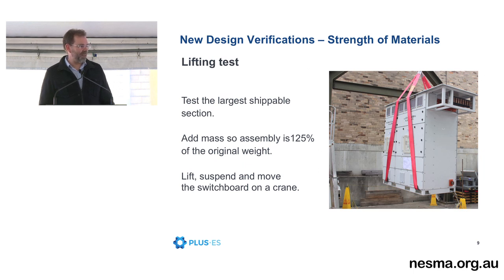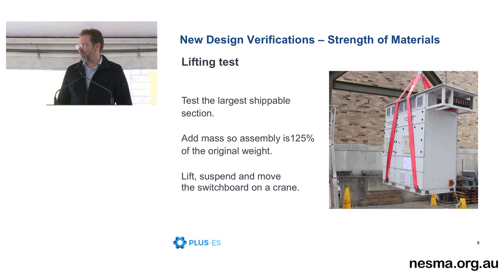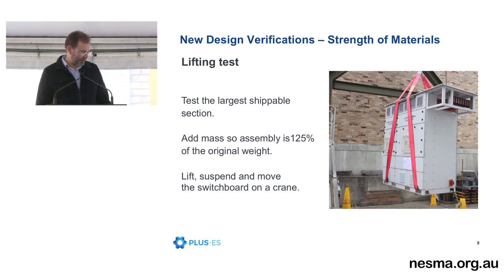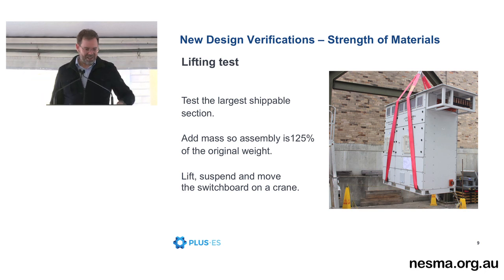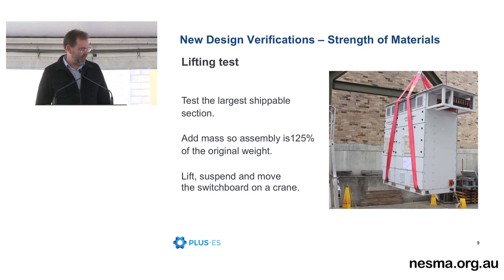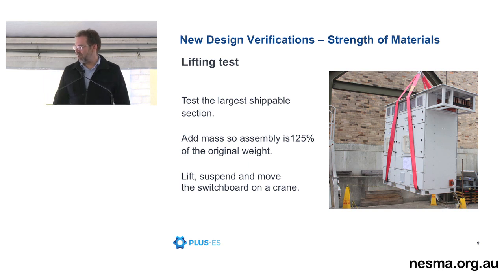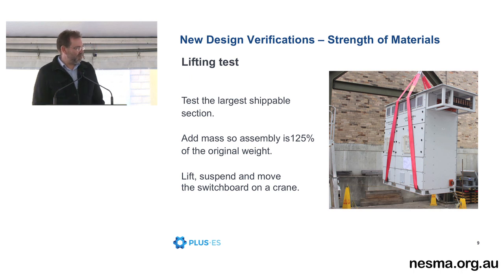The lifting test. I think it's not a bad test, this one. I know switchboards are probably only lifted twice, I suppose, in and then out. But nonetheless, you don't want the switchboard, with the eyelets poking through the top of the sheet metal, to pull through. Probably not a bad idea to test it. So they've come up with this. We add some extra weights in there. We've got chunks of concrete and bits of metal chucked in a pile ready to weigh up switchboards. So it's 25% heavier, and then we swing it around on our crane, and you've got to sit it up there for half an hour, and then you've got to move it backwards and forwards at certain speeds. So yeah, it's a lifting test.